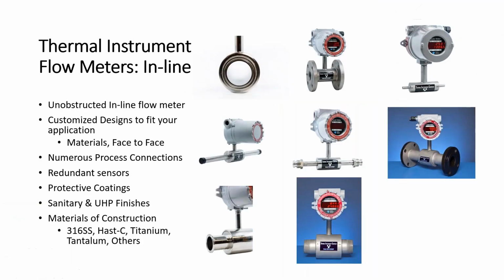One of the things I'd like to do here is point out where some of our unique designs at Thermal Instrument Company may be able to help you, because when we design our thermal instrument flow meters, we have two different styles. We have our inline style, which basically means we're delivering an unobstructed inline flow meter that is just an extension of your existing piping. Our sensors, as you can see looking at this top picture, there's nothing in the tube, nothing in the pipe. Our sensors are actually behind an inner outer wall. So they're mounted just like in that first slide. So they never come into direct contact. So that gives them nice long life.